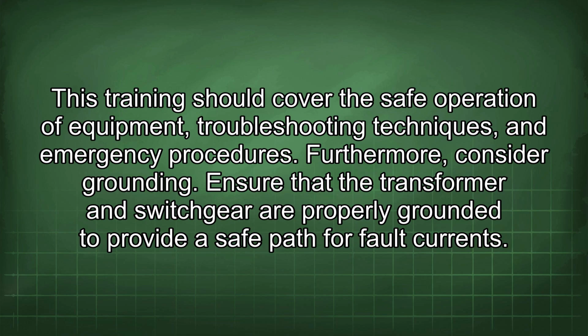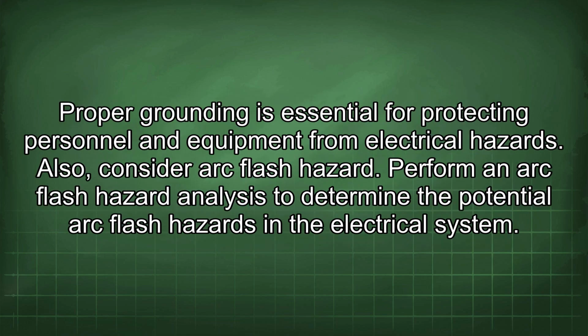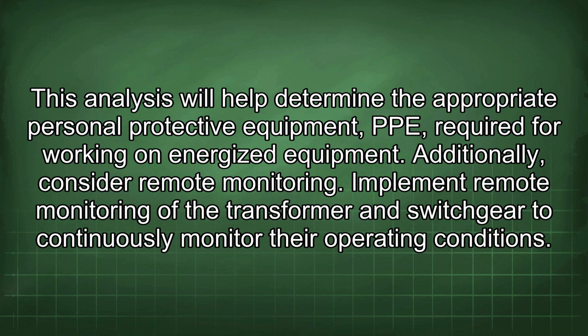Furthermore, consider grounding. Ensure that the transformer and switchgear are properly grounded to provide a safe path for fault currents. Proper grounding is essential for protecting personnel and equipment from electrical hazards. Also, consider arc flash hazard. Perform an arc flash hazard analysis to determine the potential arc flash hazards in the electrical system. This analysis will help determine the appropriate personal protective equipment (PPE) required for working on energized equipment. Additionally, consider remote monitoring.